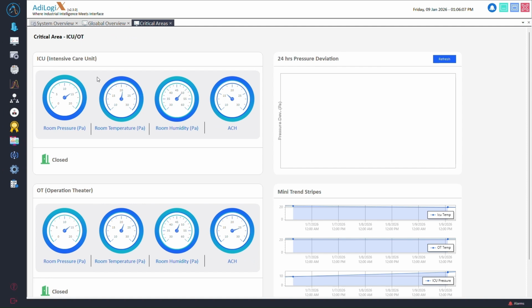This is the Critical Areas Compliance Dashboard, the most mission-critical view in the hospital building management system. At the top, we see the intensive care unit in real time. Each gauge represents a regulatory critical environmental parameter continuously monitored through BACnet IP devices. Room pressure, room temperature, and humidity ensure patient comfort and infection control. Air changes per hour verifies continuous air dilution and filtration.